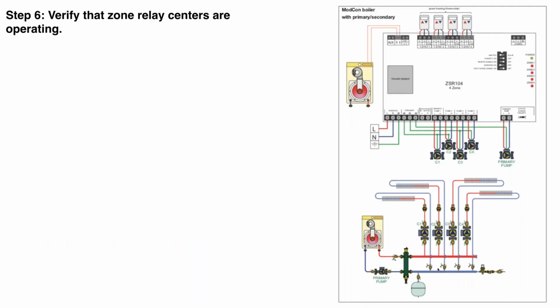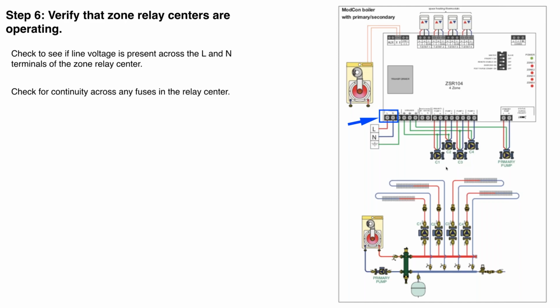Now, looking at the zone relay panels themselves, again, I'm showing one here that has 4 thermostats up here coming down to 4 circulators. First of all, check line voltage. We have line voltage to the controller. If not, something's wrong upstream. Check for any fuses. If you've got little glass fuses or sometimes little circuit breakers that are actually built into the relay panel, make sure that the fuses are not blown. Again, use your meter, do a continuity check.